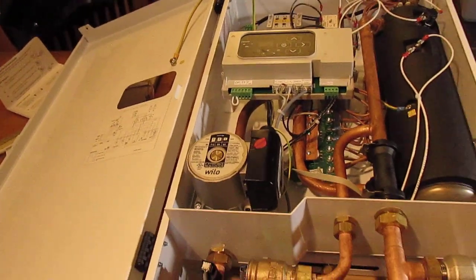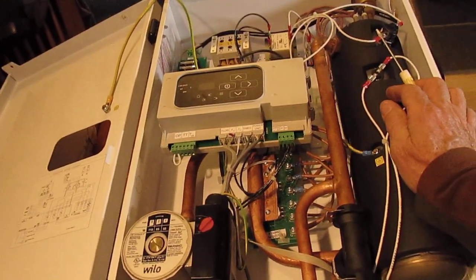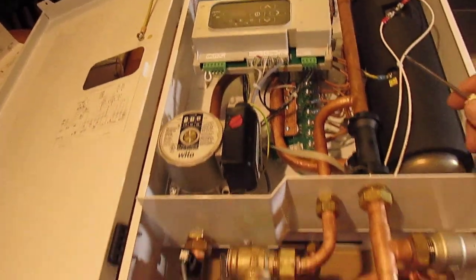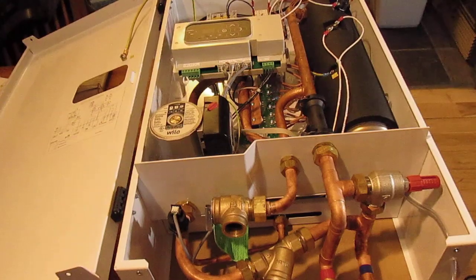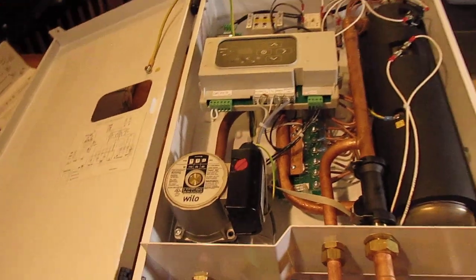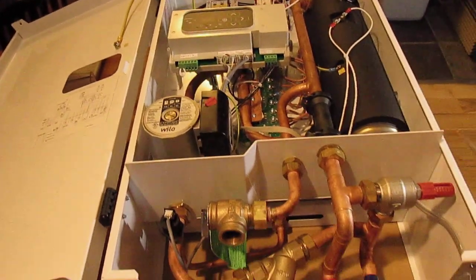Here's the heater part. This is the boiler you might call it, elements in here, and it has a computer and it has outdoor reset, which will actually be reading the temperature. The colder it is, the hotter this thing runs, warmer it is, the less warm it runs for the radiant floor heat.